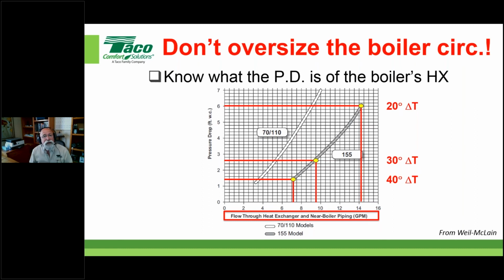You know why? Because they have no idea what you're going to do with that assembly. They don't know what's happening on the secondary side, or if there's even going to be a secondary side, or if you're just going to use it for domestic hot water generation, et cetera. So they just take a guess at what will cover them for most applications. That's why packaged boiler pumps tend to be oversized. Believe me, most of the time, even when they give you a 3-speed pump, speed 1 is often bigger than it needs to be.